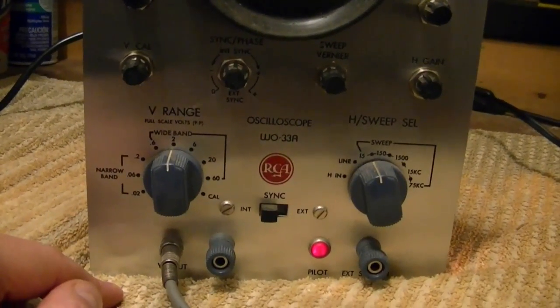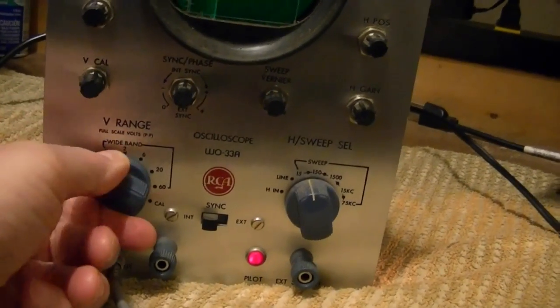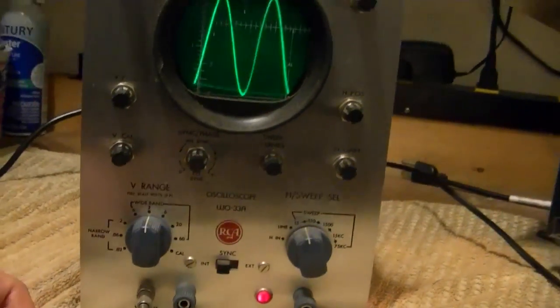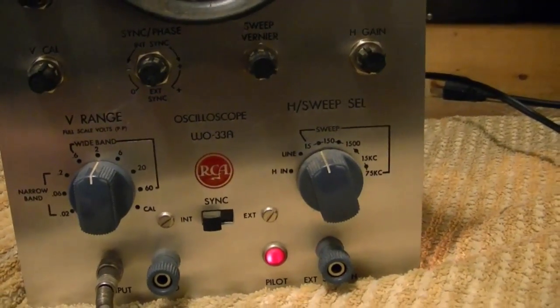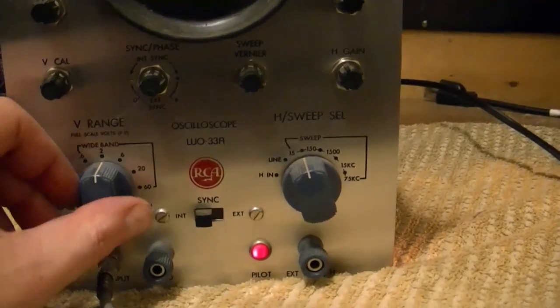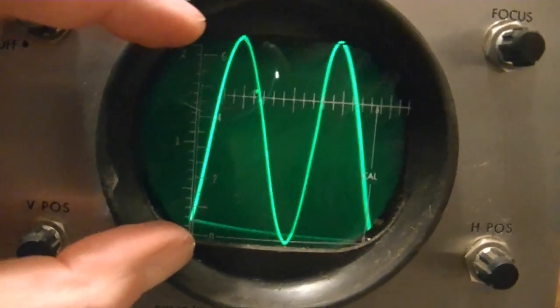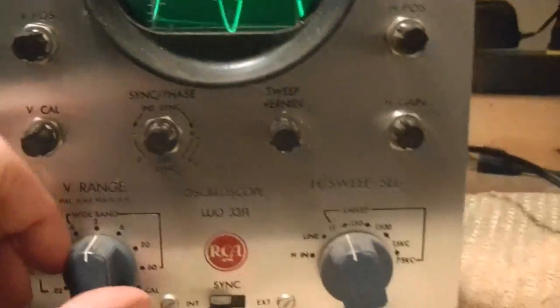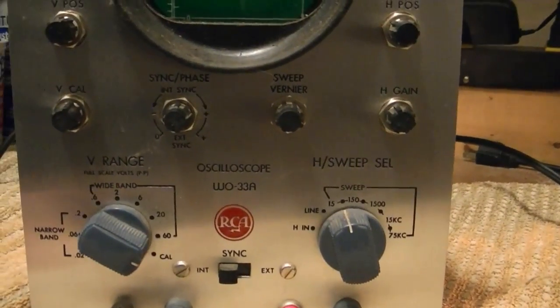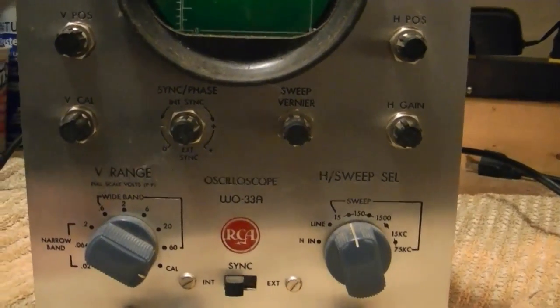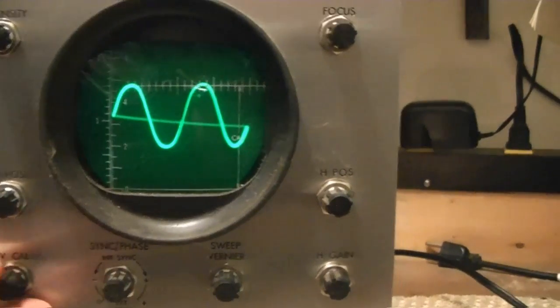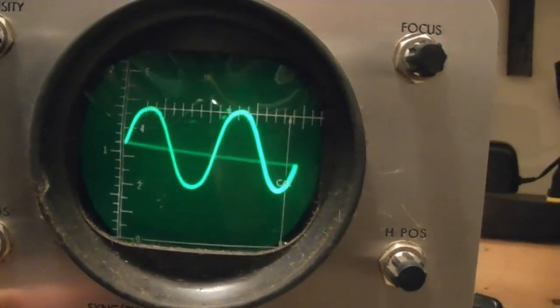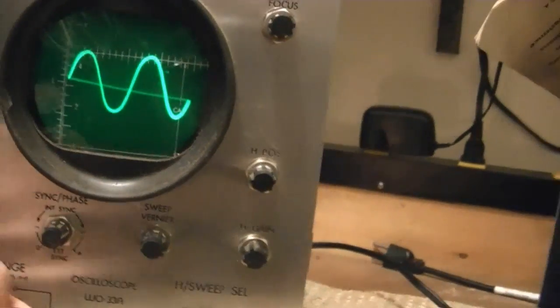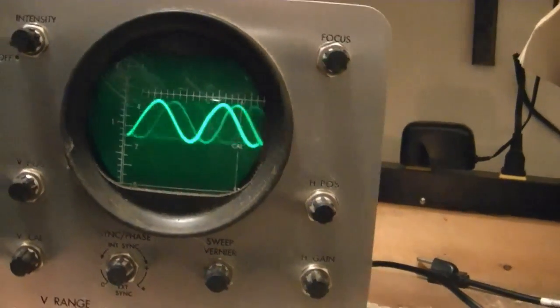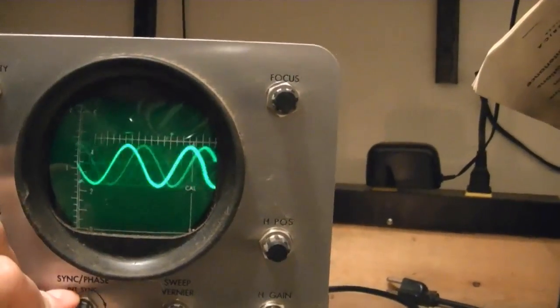And also notice this is wideband and narrowband. They call that a feature, that they decrease the bandwidth at the more sensitive ranges. Okay. Also, this might be a limitation of their amplifier design, but they call that a feature. And there's a built-in calibration mode. So this scale here, when it's calibrated, reads directly in volts. So 1 volt, 2 volts. Over in cal, it's an internal reference waveform. I've got to look up the instructions, but you're supposed to, I believe, then adjust this, maybe so it's exactly 1 volt, something like that, and then your device is calibrated. Then you can switch back to this and compare it to your input, and then read directly off the scale to see the input amplitude.